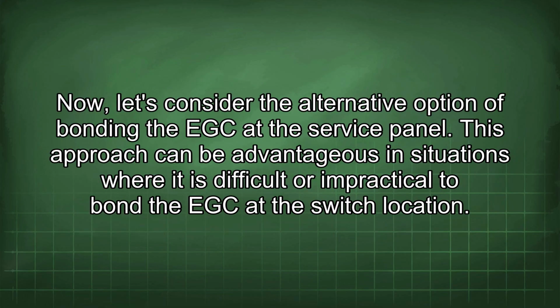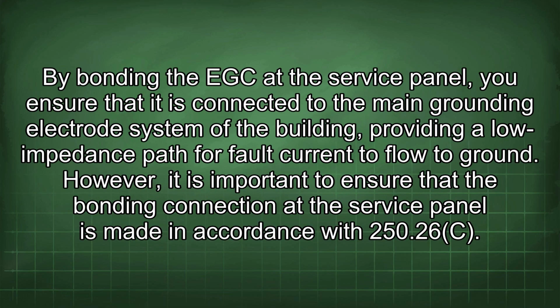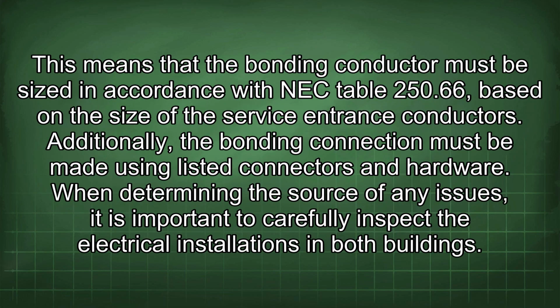Now let's consider the alternative option of bonding the EGC at the service panel. This approach can be advantageous in situations where it is difficult or impractical to bond the EGC at the switch location. By bonding the EGC at the service panel, you ensure that it is connected to the main grounding electrode system of the building, providing a low impedance path for fault current to flow to ground. However, it is important to ensure that the bonding connection at the service panel is made in accordance with 250.26(c). This means that the bonding conductor must be sized in accordance with NEC Table 250.66, based on the size of the service entrance conductors. Additionally, the bonding connection must be made using listed connectors and hardware.